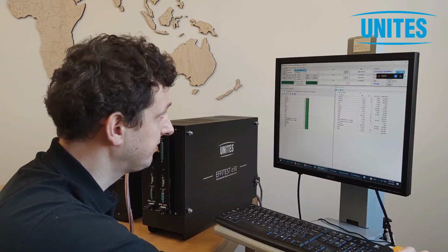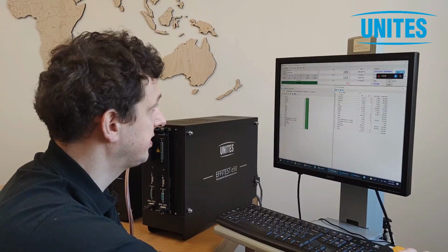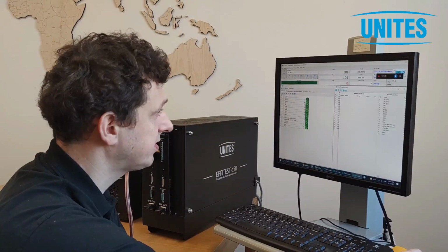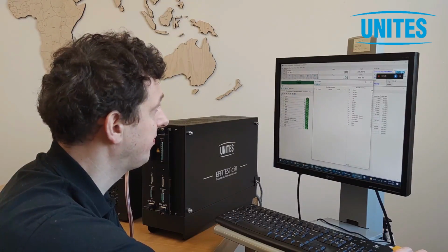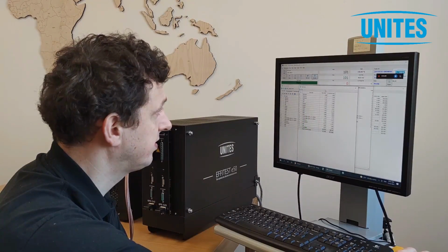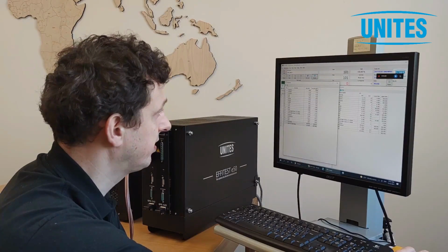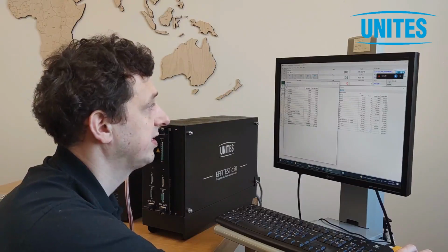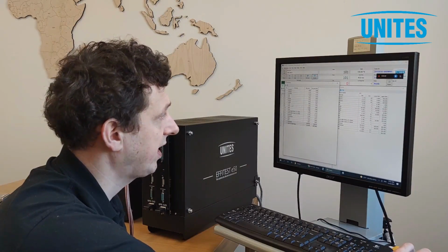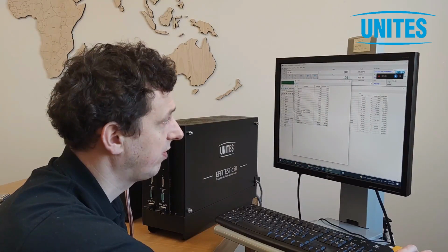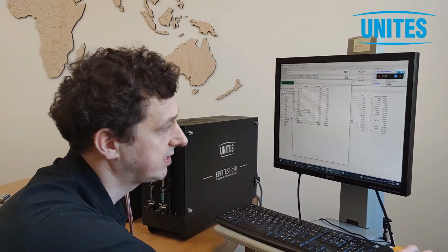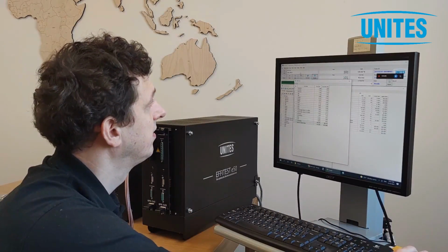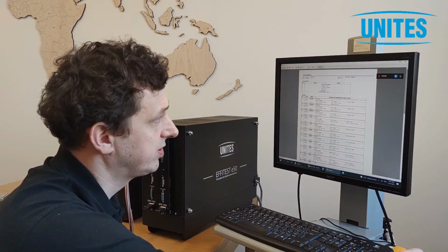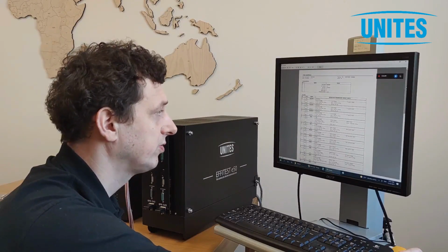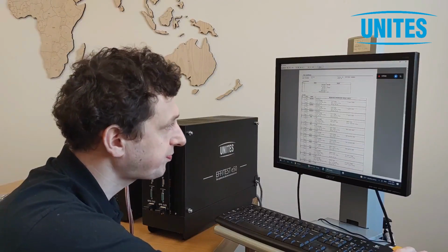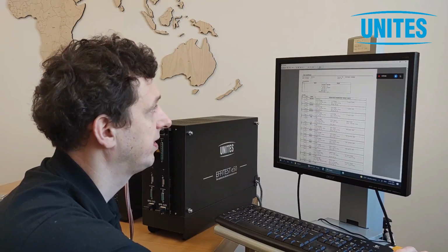I can display other items from the test properties and test results. Also the counters here, so I know how many fails and how many passes I have. Test times are also important for optimizing the test, so you can display how much time it takes to test one test step. If I need to optimize something like ICBO here, I can focus on the longest test times and see on the virtual oscilloscope if it makes sense to shorten the test time or not. And test conditions are used when you want to export automatically the test specification of the given component. You don't need to fill any external form, this is automatic again.